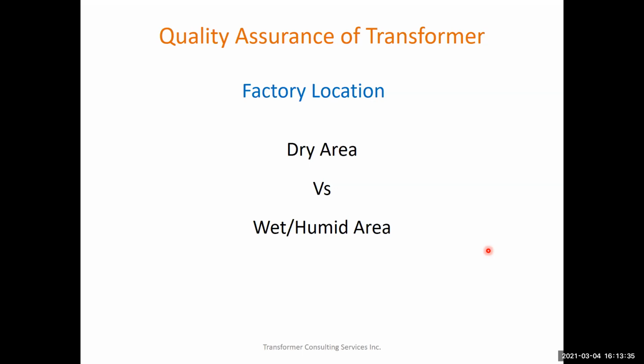As I talked about, inside the transformer there is an insulation package, which is nothing but a carbon-hydrogen chain. During the manufacturing process, if that carbon-hydrogen chain is exposed to the environment, especially humidity, it can absorb moisture from the environment. If it absorbs moisture, the manufacturer has to put the transformer into the vapor phase for a longer period, and a longer period means a cost in energy.